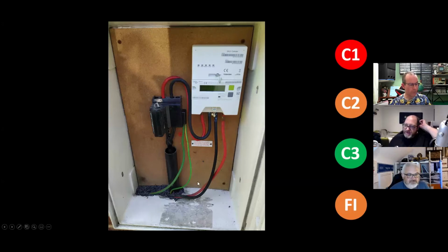Haircut. Yeah. No main earth terminal as well. Yeah, I would suggest there needs to be an insulated Henley there. I would probably ditch that and put that into a Henley and then take that one. Yeah, and I'd label the gas and the earth separately.